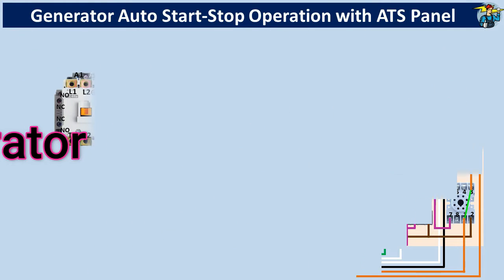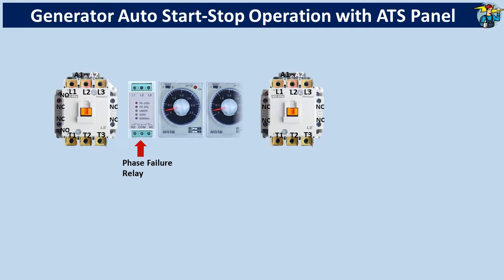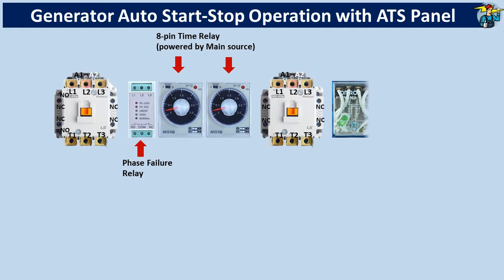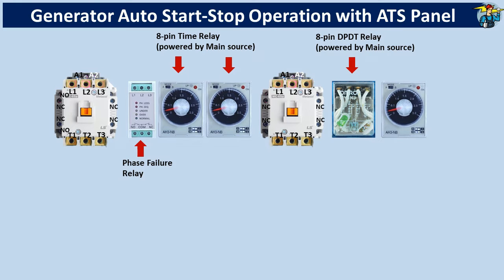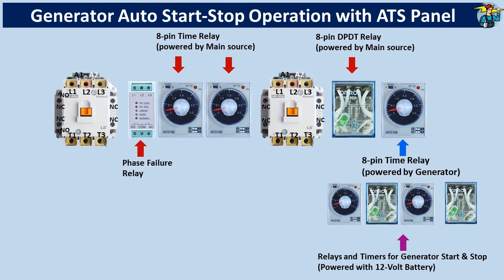We require 2 magnetic contactors for mains and generator power, and a phase failure relay to monitor any fault on the incoming 3-phase mains supply. 2 time relays and a DPDT relay operational with mains supply, and another time relay powered from the generator side. A timer and relay operational with 12V battery for generator automatic start connection.